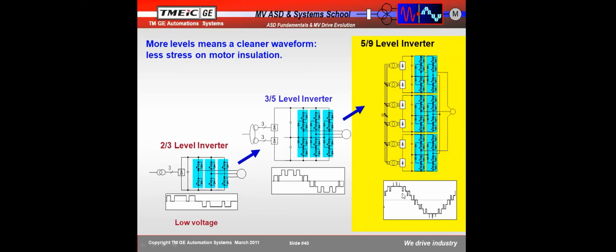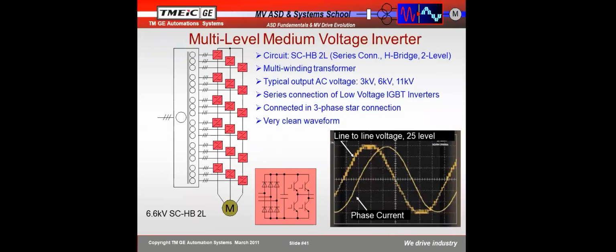So you're only turning on 1/4 or 25% of the voltage at the time. And now I think this used to be state of the art. I still think it's very, very good in terms of producing a good output waveform to the motor that's not going to cause insulation issues. Can you do better? Well, yes, you can.